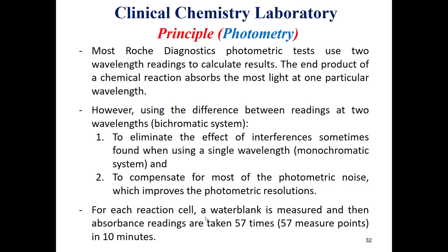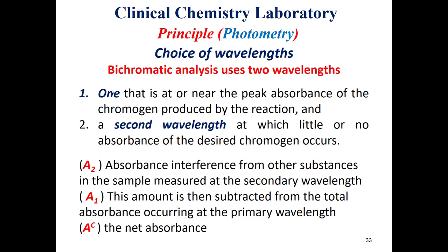For each reaction cell, a water blank is measured and then absorbance readings are taken 57 times. So in 10 minutes, we start with the water blank measurement and then make measurements at 57 points. We have a primary wavelength and a secondary wavelength as discussed.